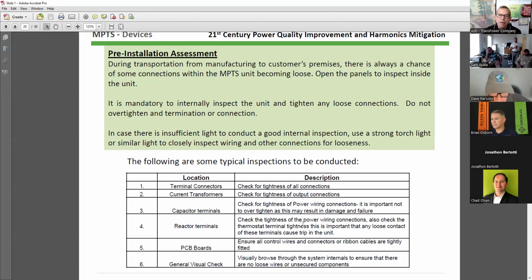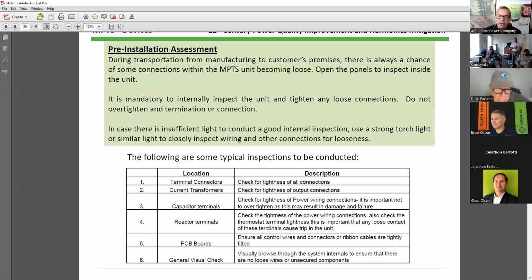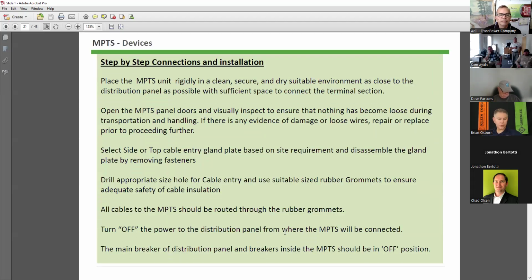It's very important because you cannot check a lot of things after you have connected, because now the electrical wiring in your building becomes part of the MPTS wiring. So when you get a short circuit or get ohms that you shouldn't have, you don't know where it is coming from. Right, Brian? That is correct, yeah. You could be measuring through transformers if you were checking continuity between the MPTS terminals when they're already connected.